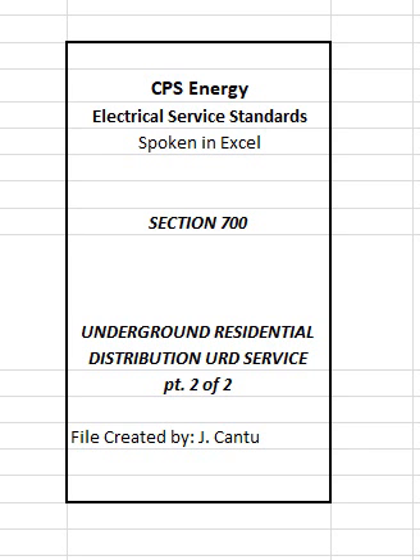704 CPS Energy inspections. Where customer elects to use their contractor to install the service lateral conduits, the service trench and conduit installation must be inspected by a CPS Energy inspector prior to backfilling the trench. City inspectors or other AHJ inspectors do not perform these inspections. To schedule an inspection, customer may contact the CPS Energy customer service representative or refer to helpful numbers listed on the inside front cover page.